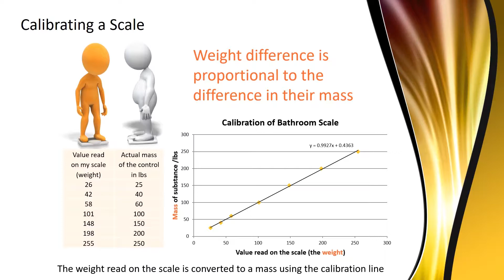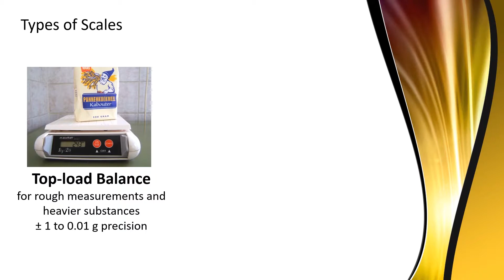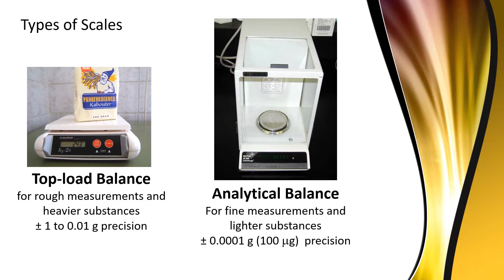What I want you to get out of all of this is that we can be confident that we measure the mass of matter when we read the value on a laboratory scale, since the scale has been calibrated against known masses. As far as the different laboratory scales used in the lab, the most common instruments are either a top-load balance, which is utilized for rough measurements of heavier substances, giving us a precision of plus or minus 1 gram to 0.01 gram, and analytical balances, which are used for highly precise measurements of lighter substances with typical precisions of around plus or minus 0.0001 gram or even smaller.